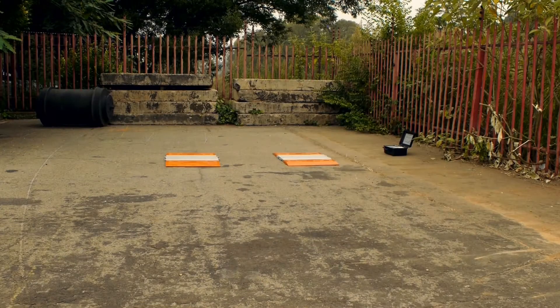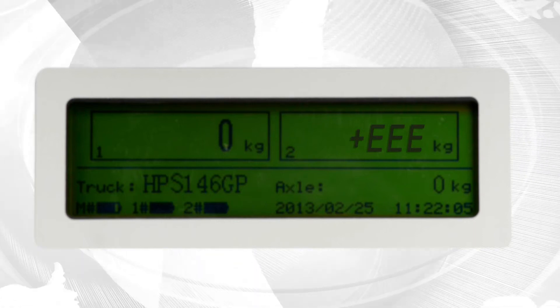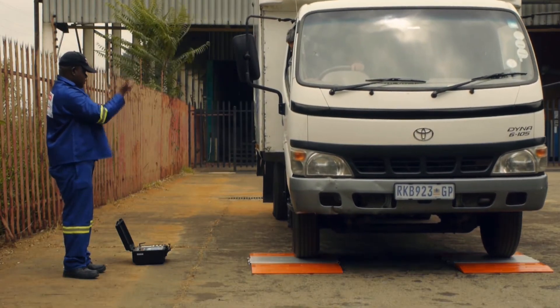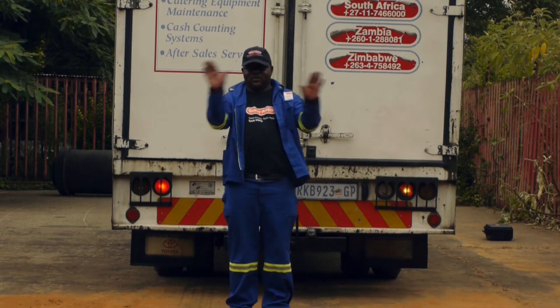The approach on either side of the pads must be level and have a minimum distance greater than the distance between the axle groups of the vehicle being weighed. Failure to adhere to these simple instructions will increase the chance of mass reading errors. Do not allow a vehicle to accelerate while on the weigh pads. Do not stand behind the weigh pads while a vehicle is on the pads.